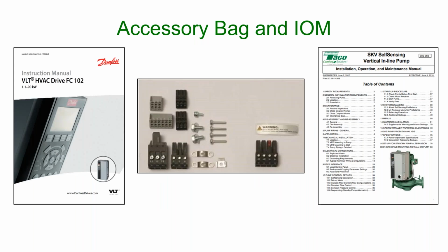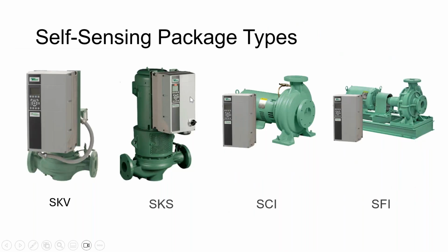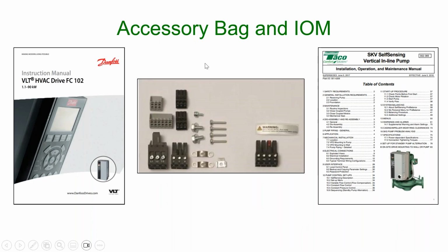So let's get into the drive a little bit more and what comes with these drives when the project is shipped, because this is very important. This is very important because sometimes this bag gets thrown out and you have to call the factory and get another bag sent out, and that's not good. So there is an accessory bag that comes with these, with the IOM manual and some hardware, as well as the instruction manual for this FC102 drive. So it's very important that somebody on the project takes hold of those bags and keeps track of them, because it has a lot of information as well as some stuff that needs to be put into the drive. So just keep that in mind.